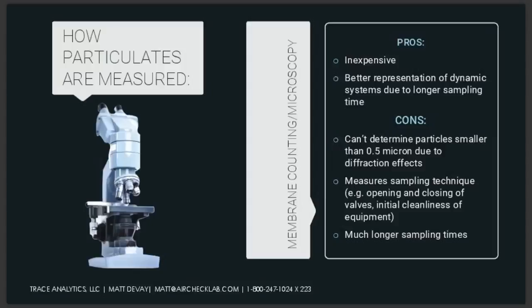The other thing about membrane counting is it collects particles not just while it's connected to the system, but basically from the time that you unseal the cap on the membrane housing until the time that you put that cap back on. So if you're working in a mill of some kind and you've got a lot of particulate in the air, or if you're using valves, ball valves in particular can be not a very good match for membrane microscopy. It's going to measure your technique and your equipment as well as your air. And so that's a common pitfall that you can have with these. The other thing about them is if you've got stricter classes that you need to meet, if you're going to try to meet an ISO class 1, expect to have that membrane hooked up to your system for quite a while.